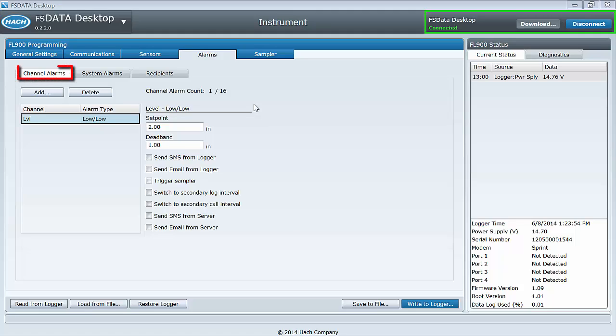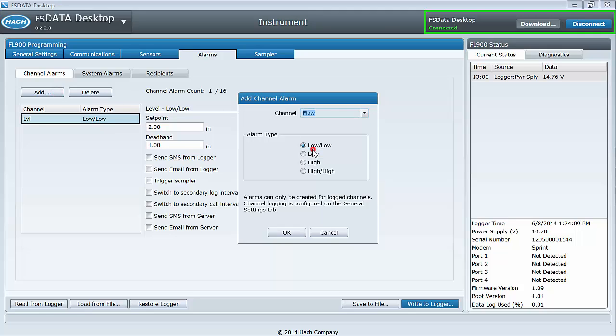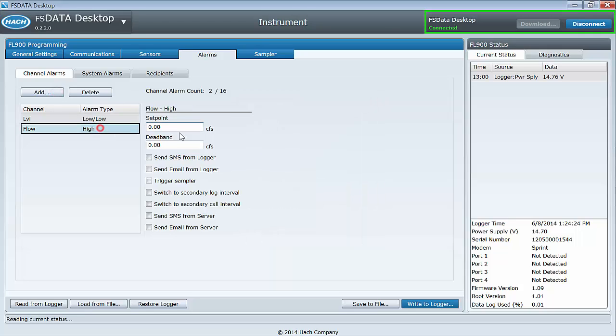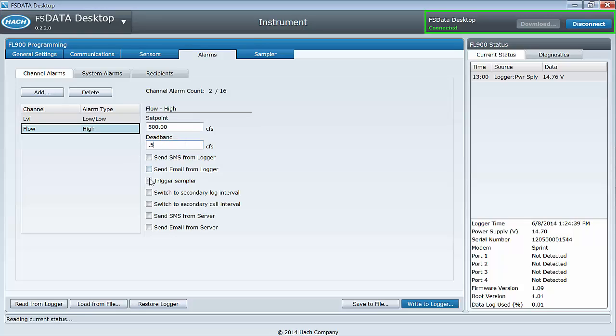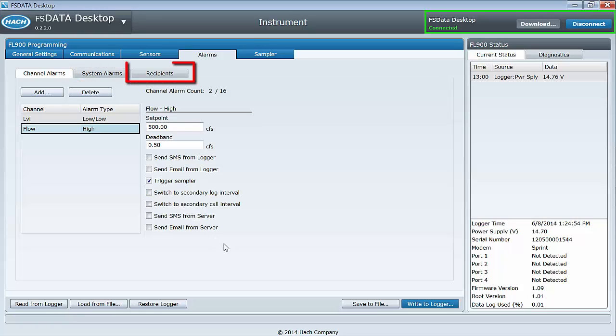Channel alarms refers to logged channels within your logger. Only logged channels can have alarms assigned to them. Click Add and then select the channel and the alarm type. Now select the alarm trigger, deadband, and alarm output. Up to 16 alarms can be set. System alarms can be set on the next tab, and the email or SMS recipient list is on the last tab.